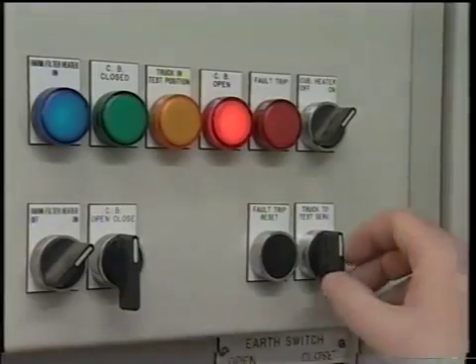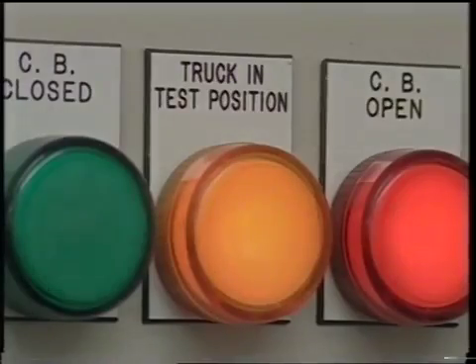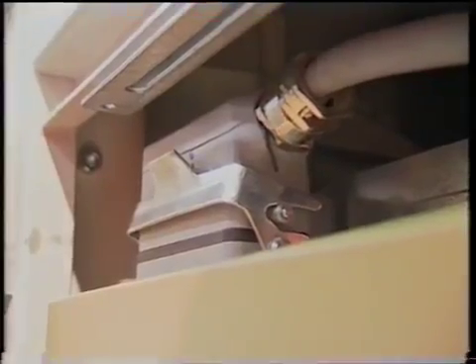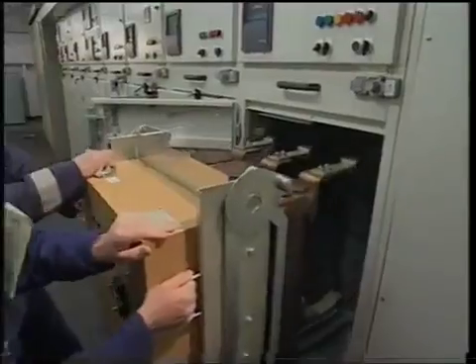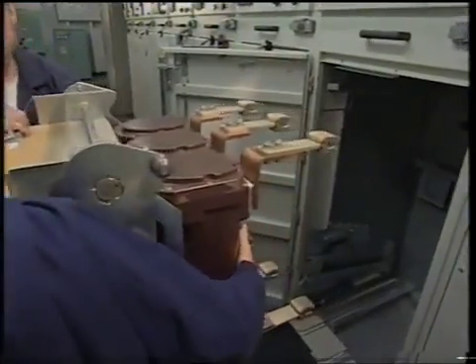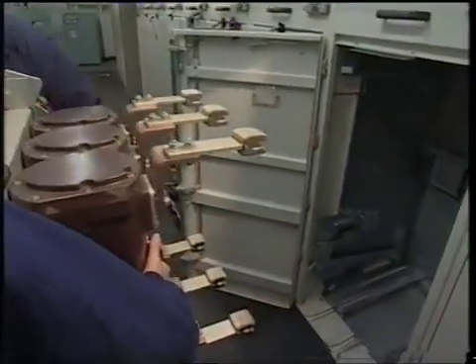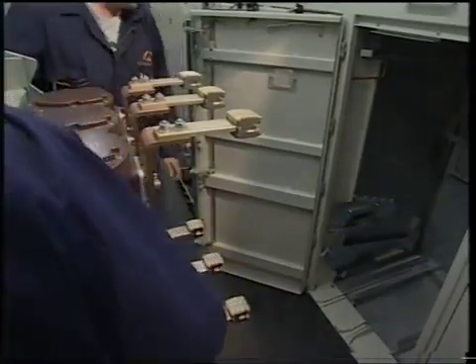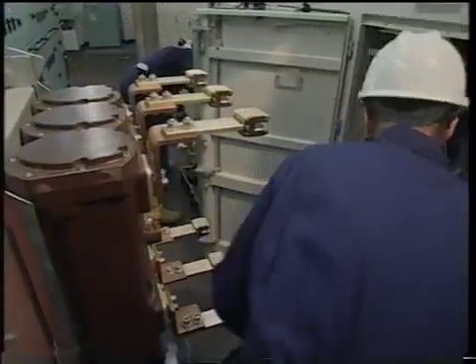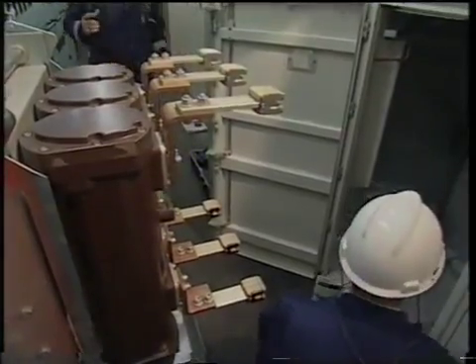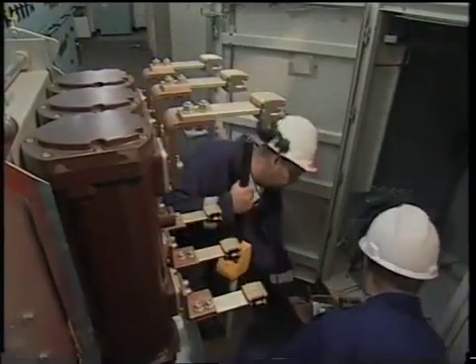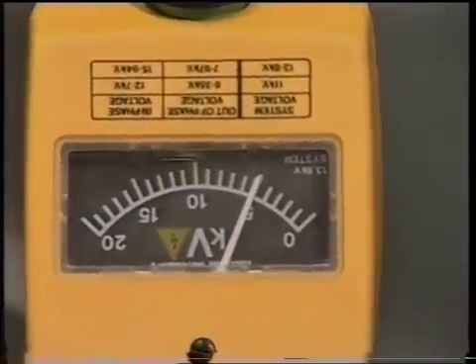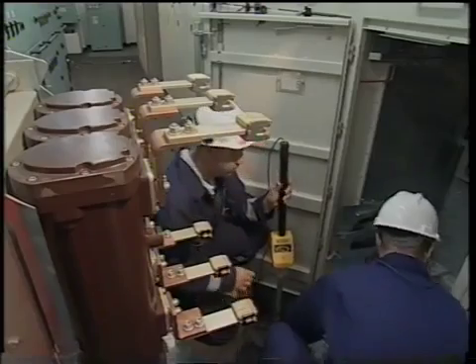The circuit breaker is isolated by firstly switching to the test position, then opening the cabinet and removing the auxiliary umbilical connector, and then by manoeuvring the breaker out on its truck. The circuit is confirmed dead using the high voltage test prod. Firstly, it is checked for correct operation using a special test unit. Note that this check must always be performed before and after using the HV prod.